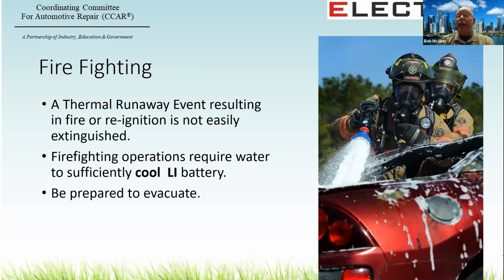For those of you that have fire sciences in your programs, this might be interesting. Thermal runaway resulting in fire or reignition is not easily extinguished. Firefighting operations may require in excess of 2,500 gallons of water to sufficiently cool and extinguish a high-capacity lithium-ion battery. The use of firefighting agents, your class A, B, C, D foam or halon, simply do not possess the cooling ability, the heat sink ability of water.